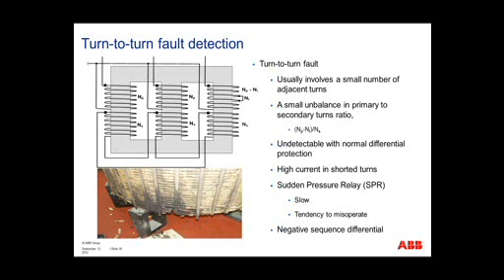Turn-to-turn fault detection. Turn-to-turn faults are when two windings in the same phase actually touch, and I'm trying to represent this by this NT. If this was a 20 to 1 winding transformer, and these two windings touch, instead of a 20 to 1 transformer you have a 19 to 1. All the flux and current that was shared between these two windings is now going through one new winding.